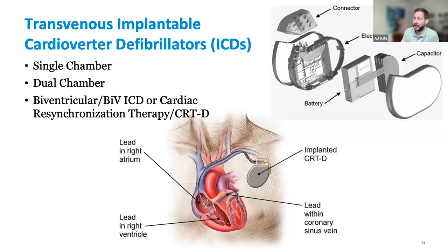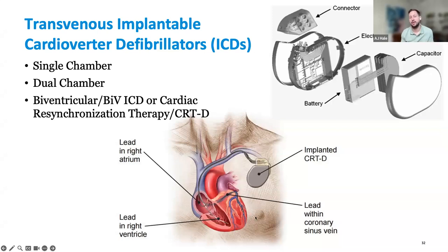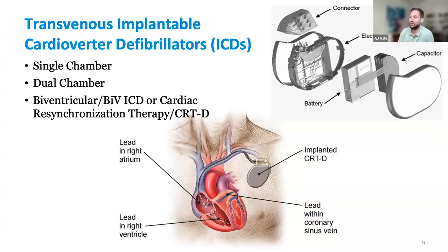Defibrillators come in single chamber and dual chamber. This one is a CRT — you have your RV lead, your RA lead, and your coronary sinus lead as well, fed down to pace the other side of the heart. The idea is to engage as much tissue as possible and alleviate the dyssynchrony that the patient may have with their electrical conduction system.